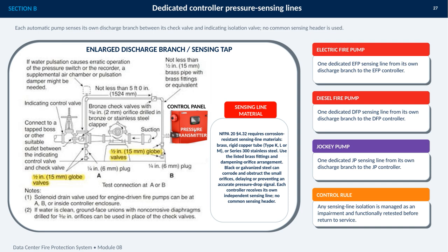Each sensing point is taken from the pump's discharge branch, between the check valve and the indicating isolation valve. That arrangement avoids a common sensing header and keeps each controller responsive to the pressure conditions of its associated pump. Material selection is also important.